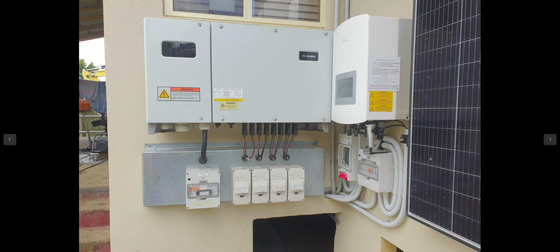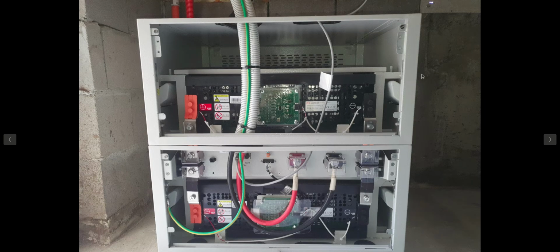And I don't know where the earth is. I actually have a big ass earth going, 16 mil. 50 mil cables going to the battery. So that must be, again, a photo before the end of the job. There's the battery. Big 15.4 kilowatt hour BYD battery. That one there is bulletproof as hell. That one can go off grid.